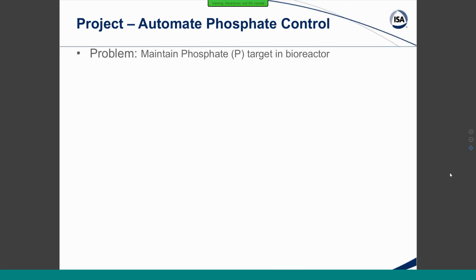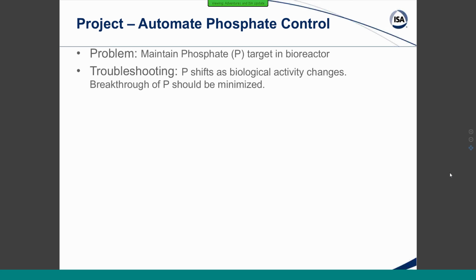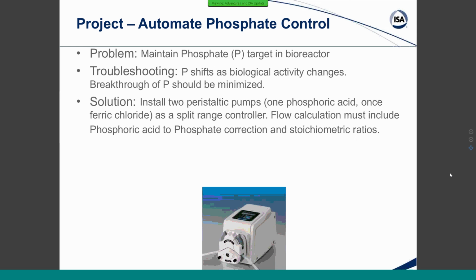Out in our wastewater system, because we do have a wastewater plant here in addition to the other utilities that we have to run, we were looking to maintain our phosphate rate. So this is a phosphate target. What makes phosphate control kind of complicated is that this is all going to be based on your biological activity. So we needed to minimize breakthrough of the high phosphate, just to control what was going out in the water leaving the plant.